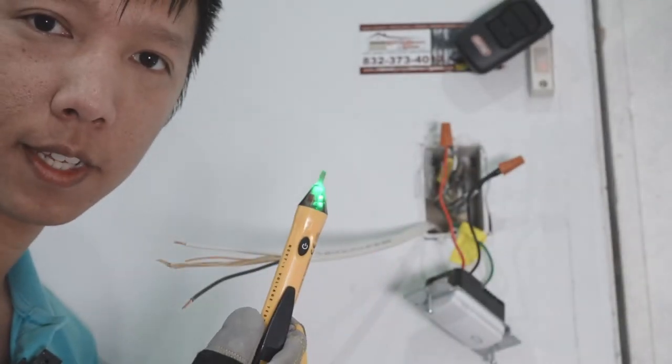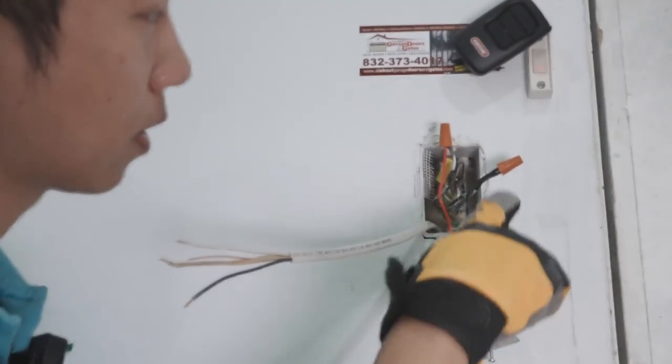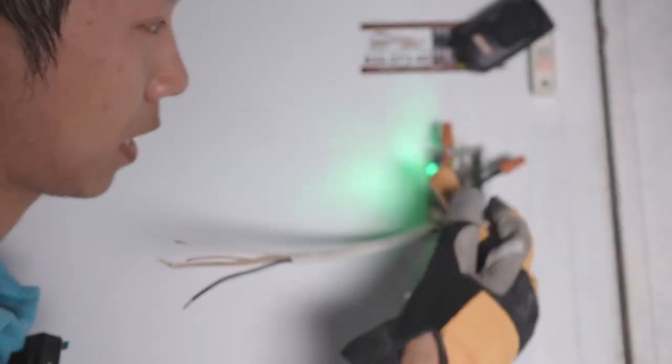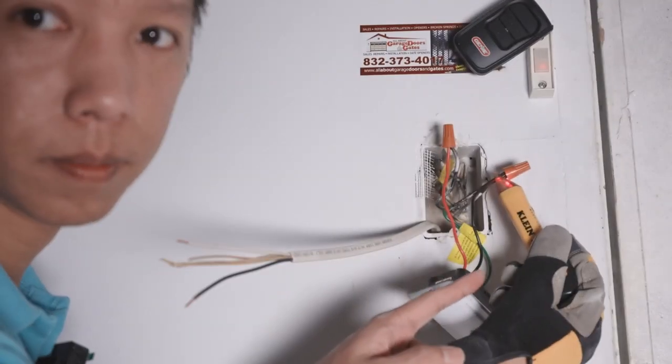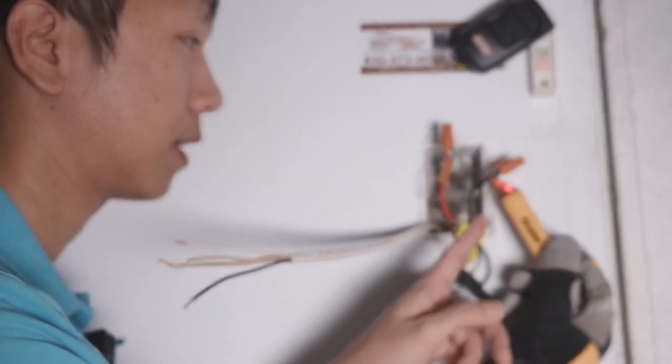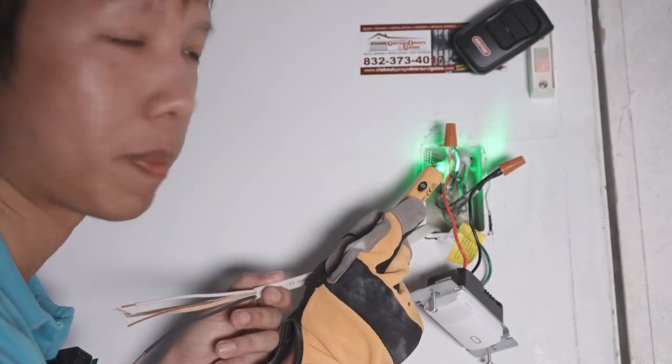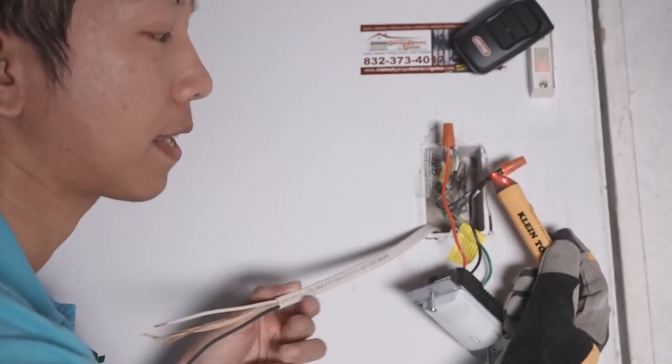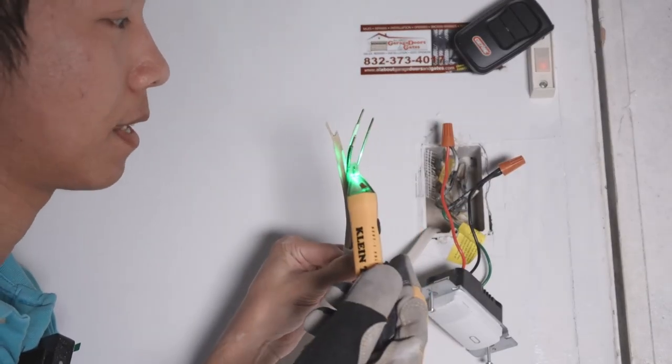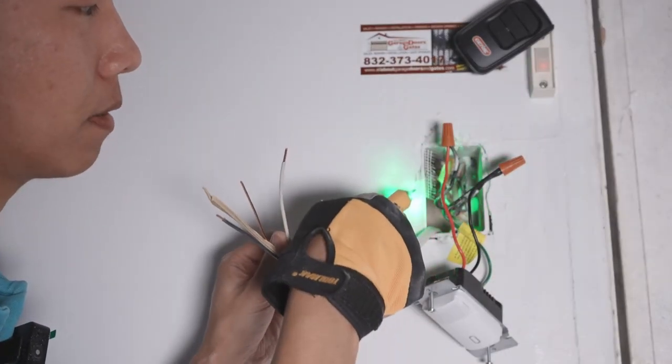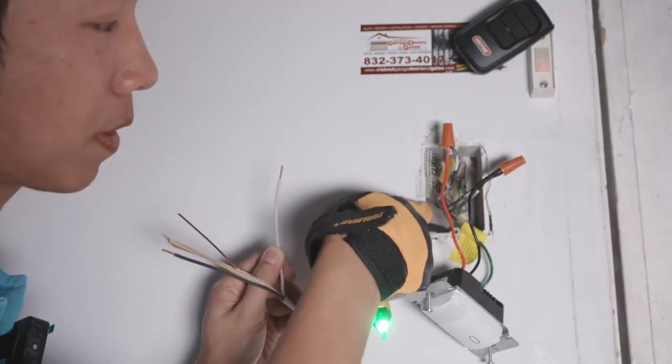We're going to use this tester pen to check which line has the power even though the light is off. We're going to turn off the light, we're going to use our pen and check. This one here has the power. This one here does not have the power. So we're going to connect our outlet cable, the black side to this one, the ground one to the green together, and the white one to the white one that is inside.